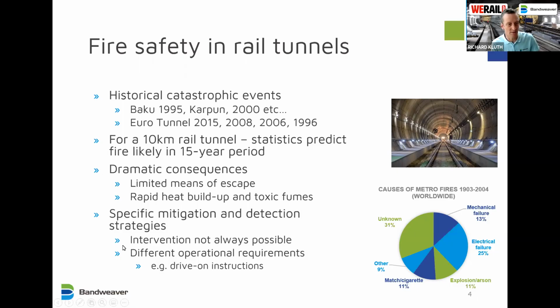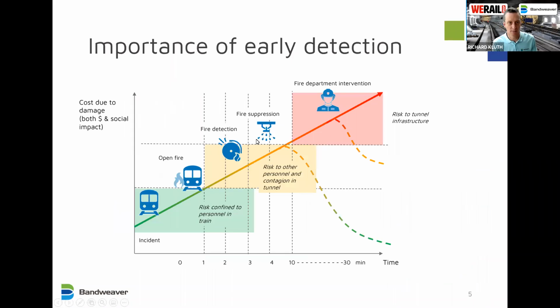You can't always intervene, you can't always extinguish at all points in the tunnel, so it's very difficult. And there are different operational requirements as well. So if we take the example of drive on, do you drive on, or do you not drive on? Prior to the 1996 fire in the Eurotunnel, they did drive on. Afterwards, they decided to stop and evacuate. So in order to form such policies and strategies, operators need to have the best information possible, and linear heat detection forms a key part of that strategy.